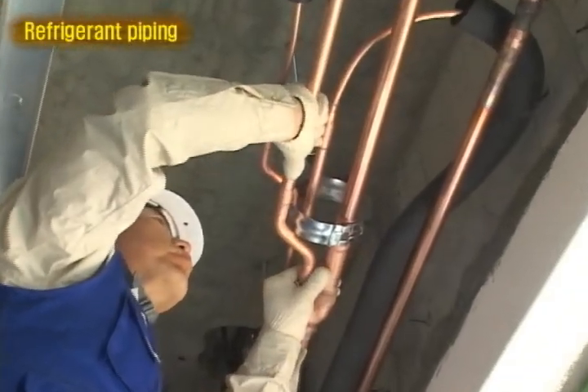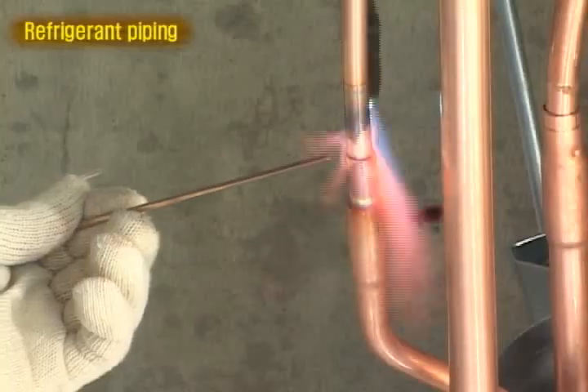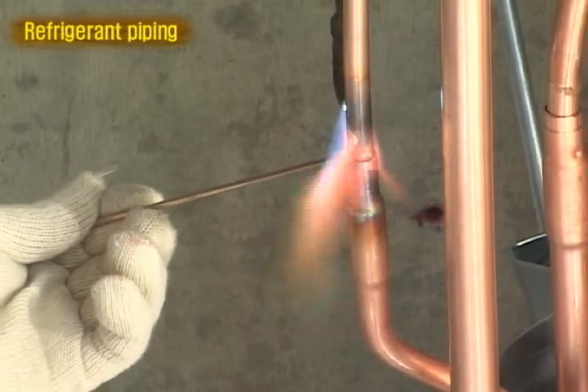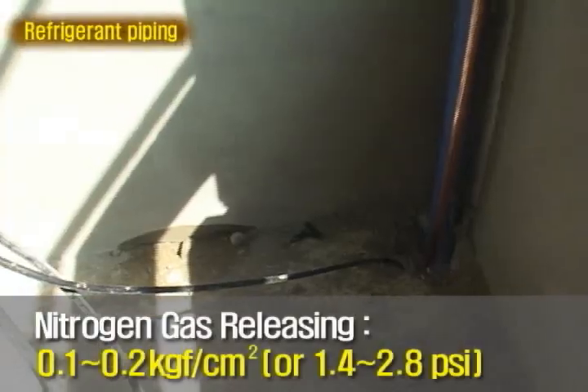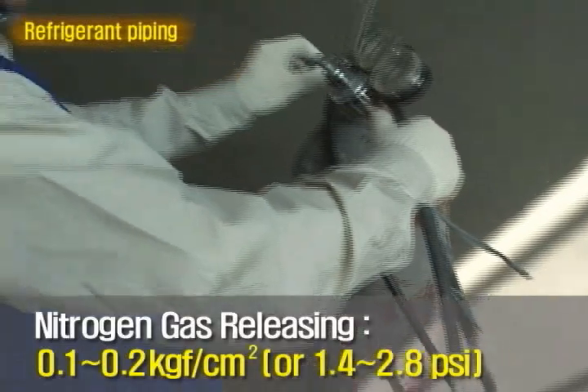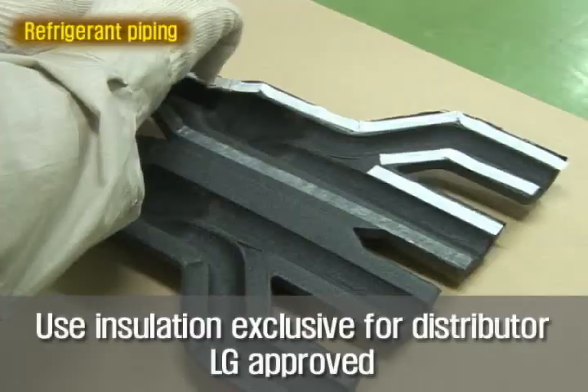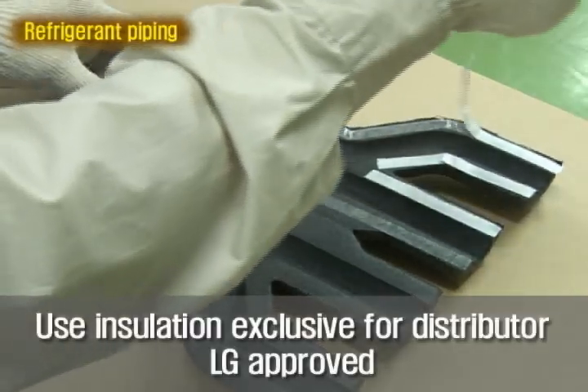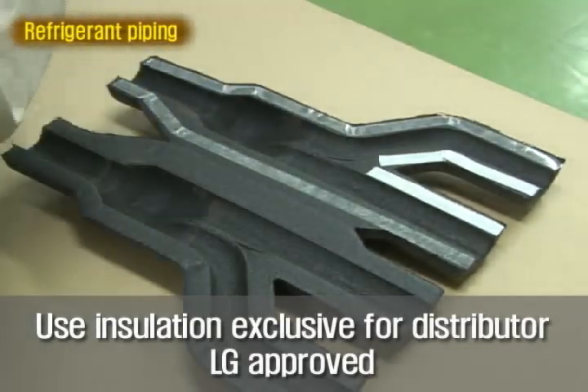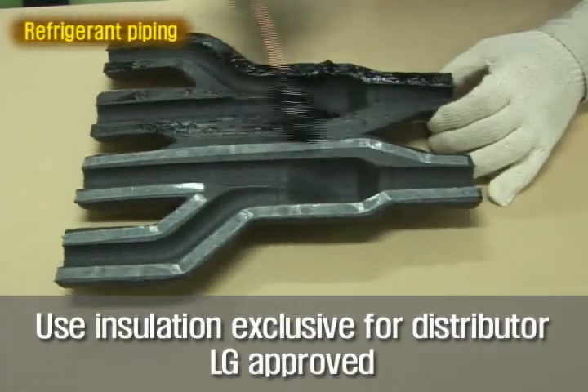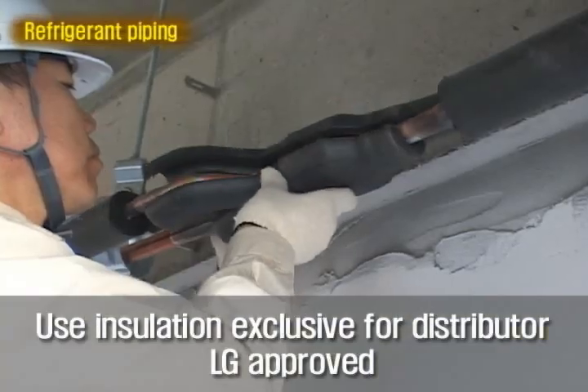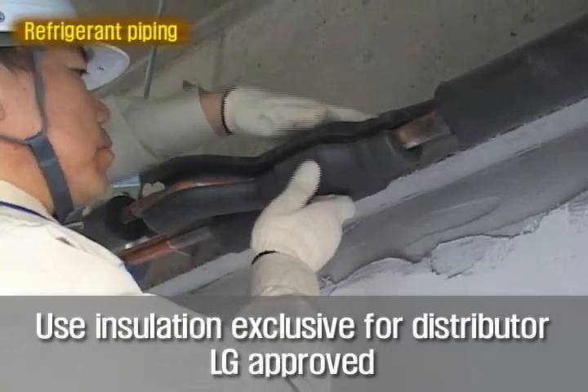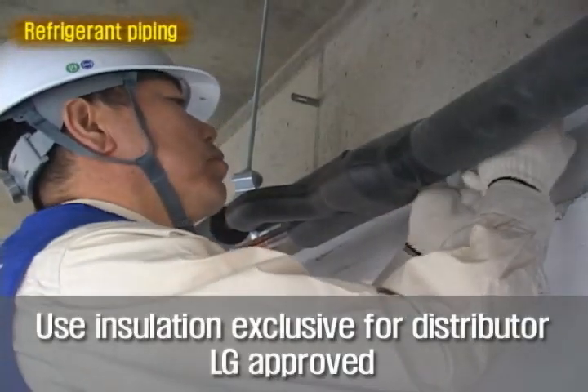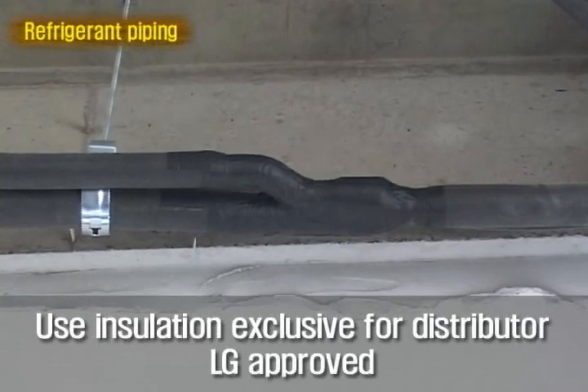Insert a pipe into an expanded one and braze them with melted solder, releasing nitrogen gas into the pipe. Remove the detachable paper from the insulation and paint some adhesive on the other side to wrap up the Y branch. Stick finishing tape on the adhered part first and wrap it all.